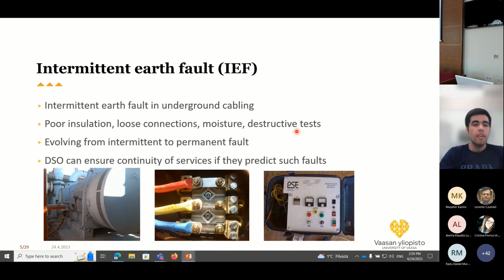And in industry, for example in a refinery, we may have 1,000 induction motors and maybe only about 10 MV motors, and chemical and process engineers know how important these motors are. So detecting and locating earth fault and intermittent earth fault in the cable can be of paramount importance, because if we lose the feeding of these motors, in fact we are losing another 1,000 motors in the industry, and it can put the whole system on the line.